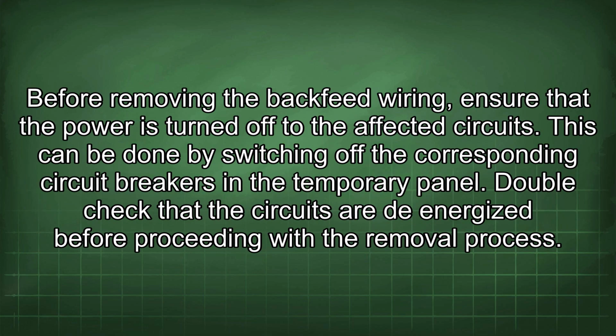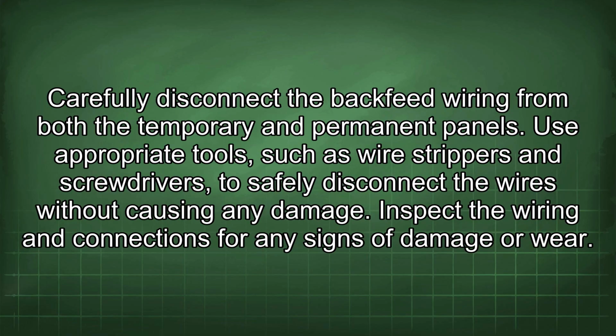Before removing the backfeed wiring, ensure that the power is turned off to the affected circuits. This can be done by switching off the corresponding circuit breakers in the temporary panel. Double-check that the circuits are de-energized before proceeding with the removal process. Carefully disconnect the backfeed wiring from both the temporary and permanent panels. Use appropriate tools, such as wire strippers and screwdrivers, to safely disconnect the wires without causing any damage.